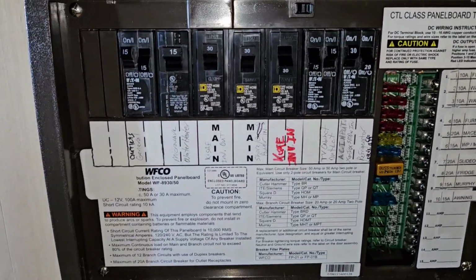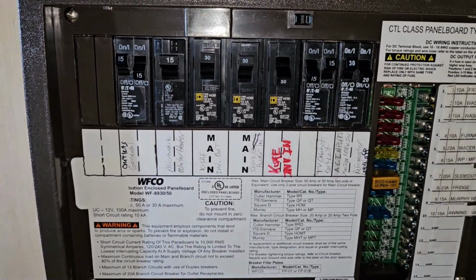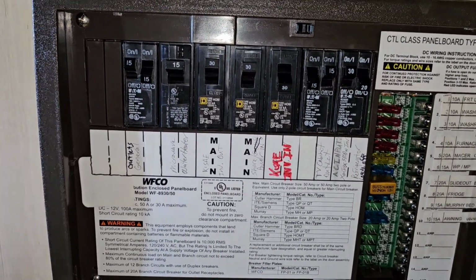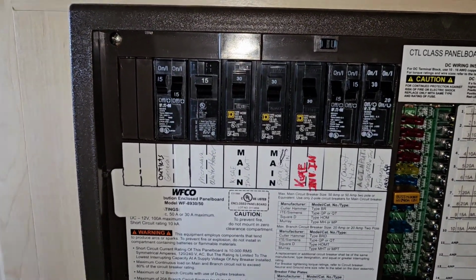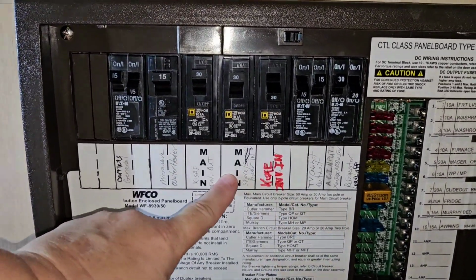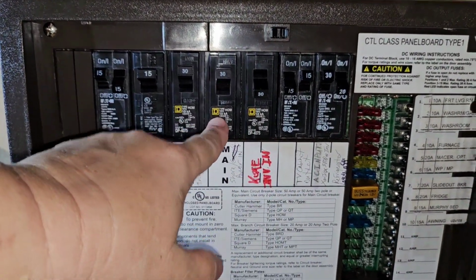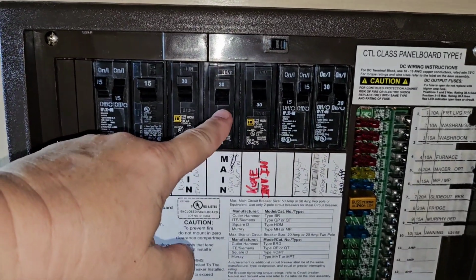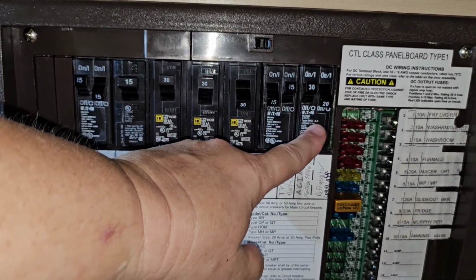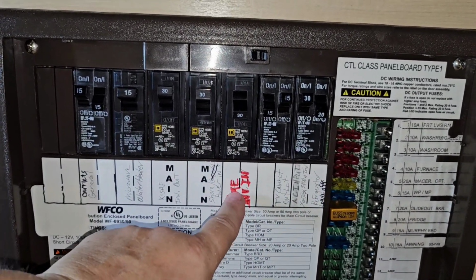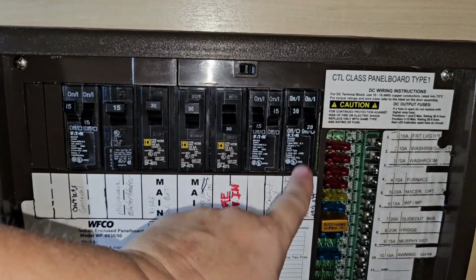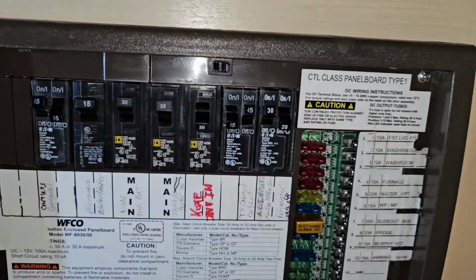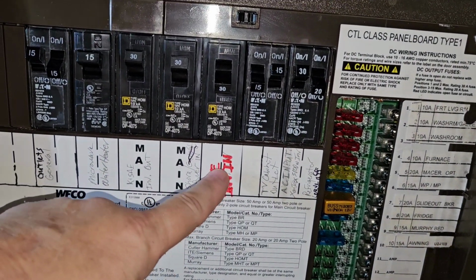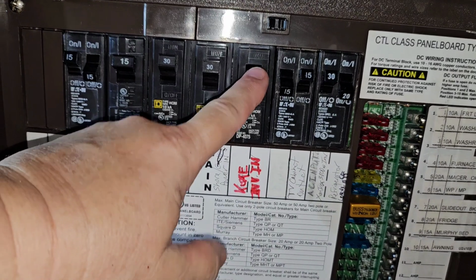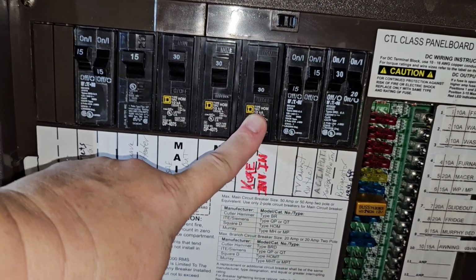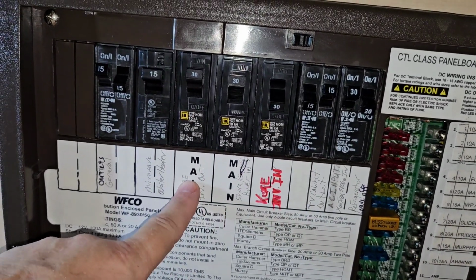Okay, so I have my panel back on. For those not familiar with the fact that I have two 3000-watt inverters, let me explain. First, my shore power comes in on a 30 amp main circuit breaker, and it feeds this bus. On this bus, I have my Kisae inverter and my Xantrex inverter, both on 30 amp circuit breakers. I leave the Kisae inverter off, so it's not taking any input from shore power. It strictly runs this bus.